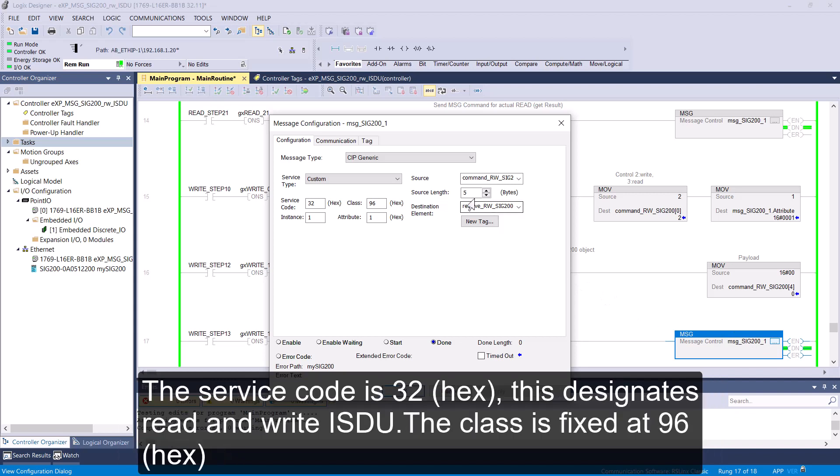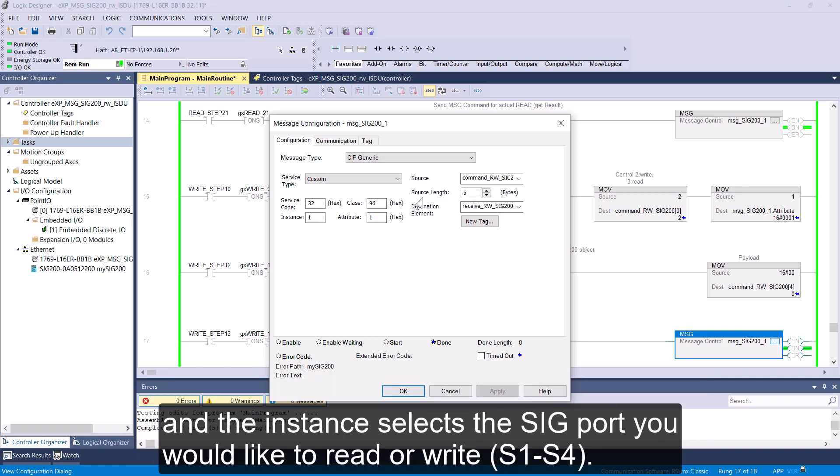The service code is 32. This designates Read and Write ISDU. The class is fixed at 96. And the instance selects the SIG port you would like to read or write to.